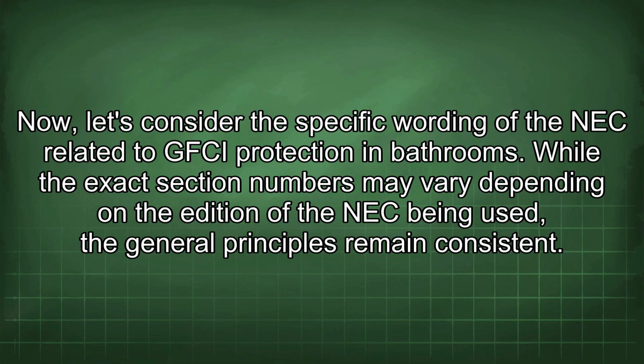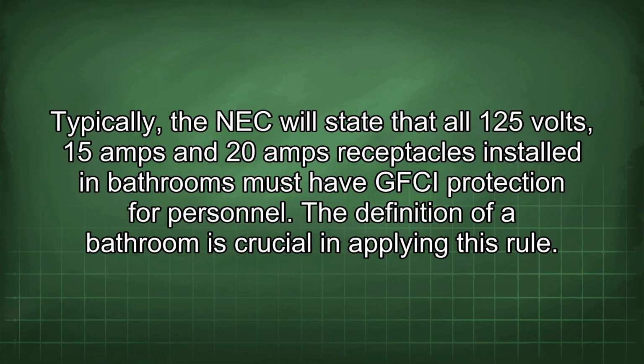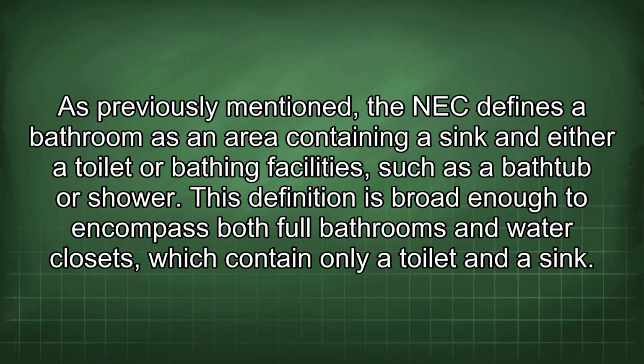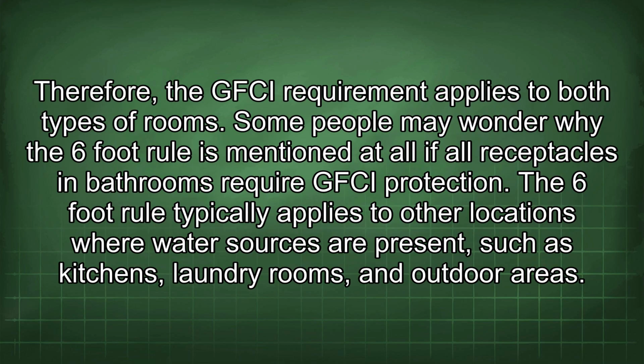Now, let's consider the specific wording of the NEC related to GFCI protection in bathrooms. While the exact section numbers may vary depending on the edition of the NEC being used, the general principles remain consistent. Typically, the NEC will state that all 125 volts, 15 amps and 20 amps receptacles installed in bathrooms must have GFCI protection for personnel. The definition of a bathroom is crucial in applying this rule. As previously mentioned, the NEC defines a bathroom as an area containing a sink and either a toilet or bathing facilities such as a bathtub or shower. This definition is broad enough to encompass both full bathrooms and water closets, which contain only a toilet and a sink. Therefore, the GFCI requirement applies to both types of rooms.